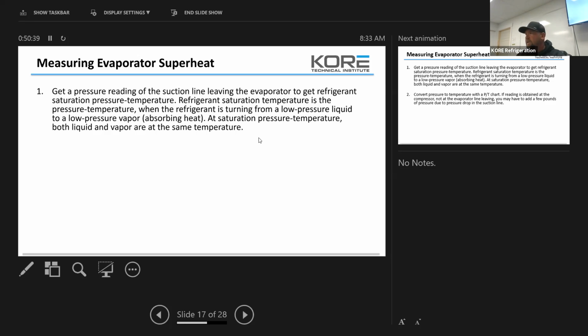So, when you're checking superheat on a small unit that's like a self-contained, that's the way you're going to have to do it, because there's usually not a port right there at the evaporator. When you're checking superheat on a supermarket, it's right there on the outlet side of the suction line, right where the TXV is usually going in. The suction line's right there coming out, bulb's mounted to the suction line. You're going to want to go on that port, and you're going to want to come 6 inches off the outlet, throw your clamp on there.